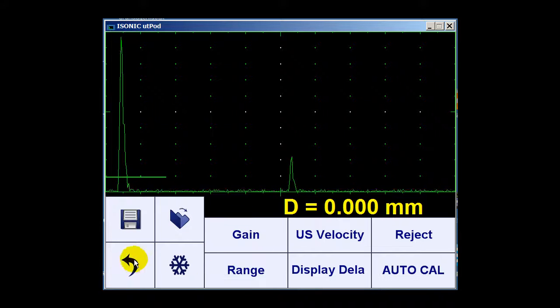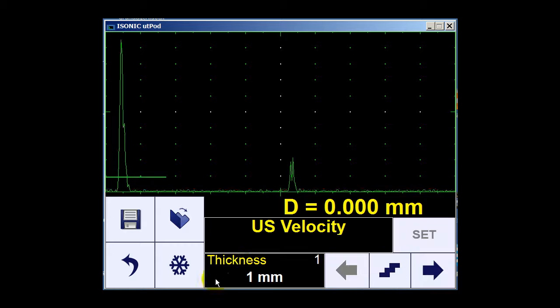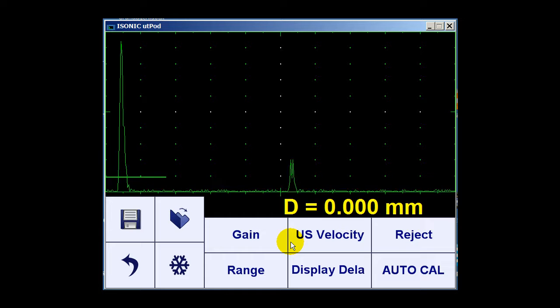Then I actually start with the auto calibration. First of all, I need to couple the probe to the calibration block just to make sure that I do a proper adjustment on the gain.